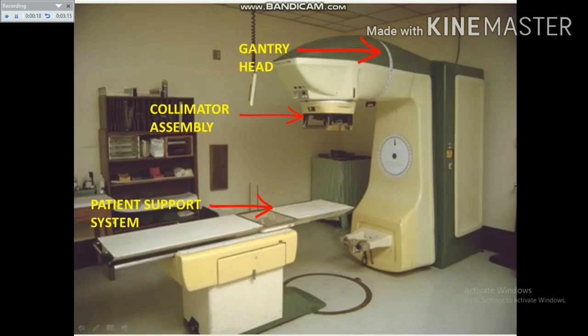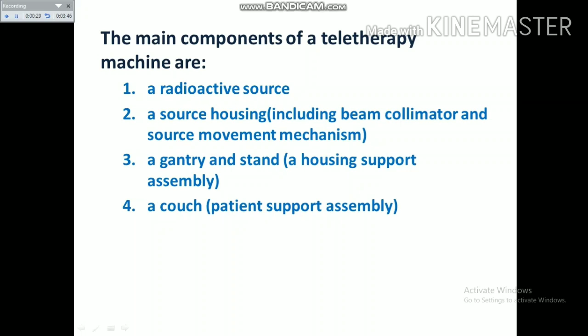The first is the radioactive isotope, which you already know, the cobalt-60 isotope. Secondly, the radiation source housing, which includes the beam collimator and the source movement mechanism. Thirdly, the gantry and the stand behind it, which will support the housing assembly of the system. The fourth component is the couch, which is the patient support assembly. And lastly, the control console.